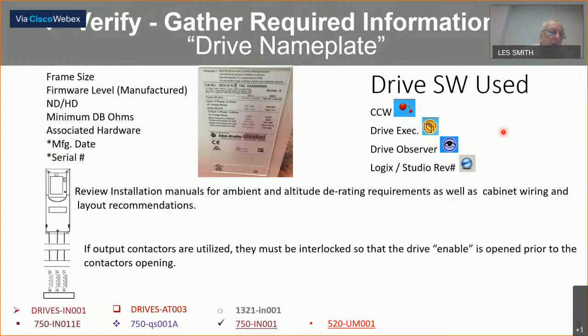Normal duty, heavy duty, this is the rating and derating of the drive needed per application. Minimum dynamic braking ohms, that will be on the nameplate, and associated hardware. Manufacturing date and serial number would be dealt with directly on a warranty basis. On the right-hand side, I encourage using software. You can use Connected Components Workbench, which is free software downloadable from the website, or Drive Executive, which is an aging software, works very nice with the older drives and PowerFlex, but will be going away in the future.